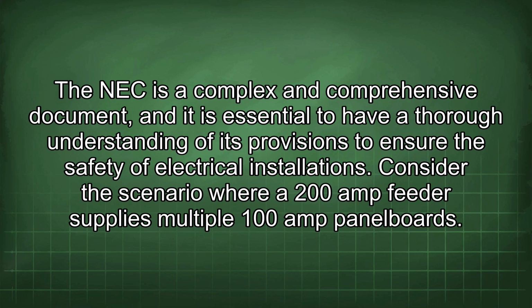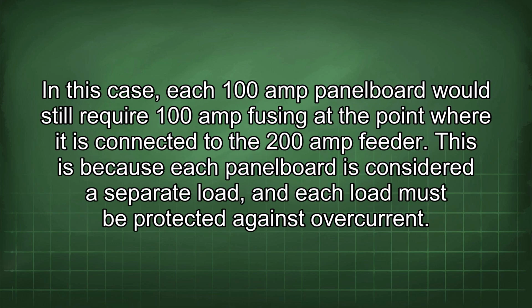Consider the scenario where a 200 amp feeder supplies multiple 100 amp panel boards. In this case, each 100 amp panel board would still require a 100 amp fusing at the point where it is connected to the 200 amp feeder. This is because each panel board is considered a separate load, and each load must be protected against overcurrent.